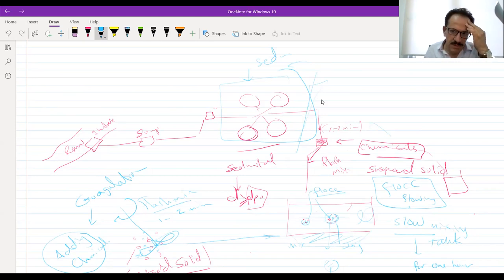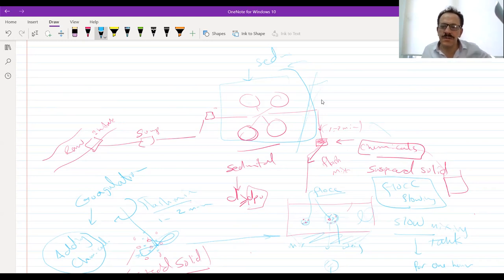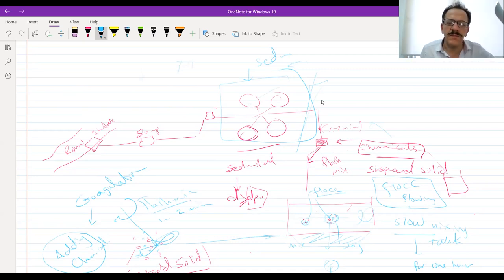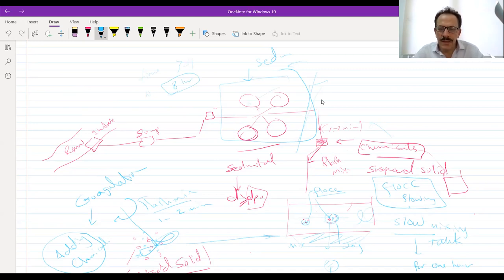In some treatment plants, they mix these two processes together — they add chemicals directly to the water and get all the settlement in one tank. In that case, you need extra volume of the tanks. For example, if the tank normally needs three to four hours detention, if you add chemicals and combine the processes, you have to wait for eight hours. That's called the clarifier — a combined clarifier that works as both a sedimentation tank and a flocculation tank.